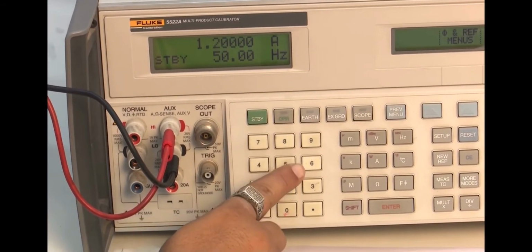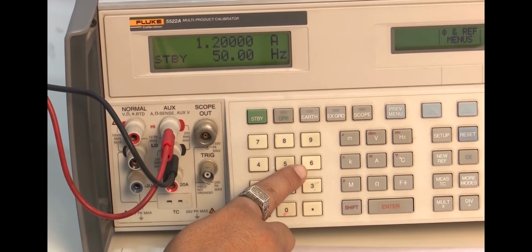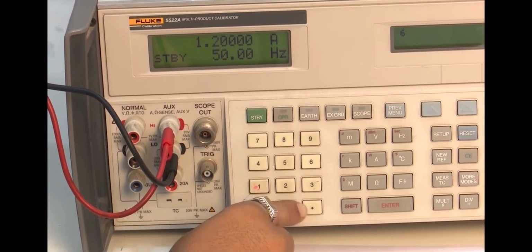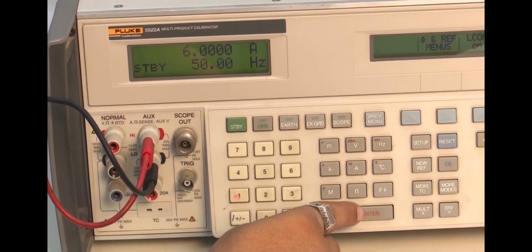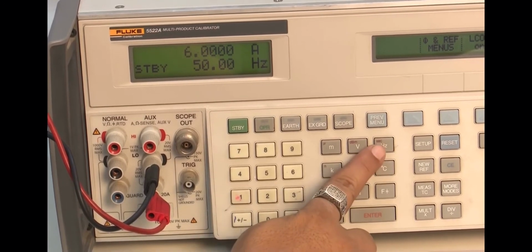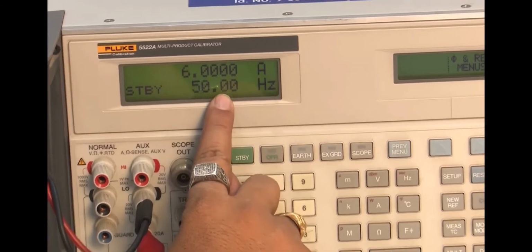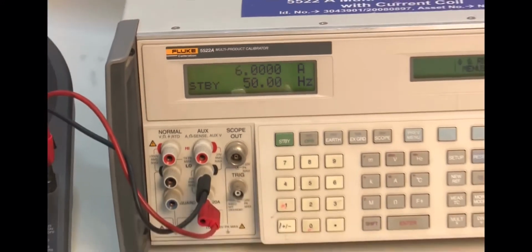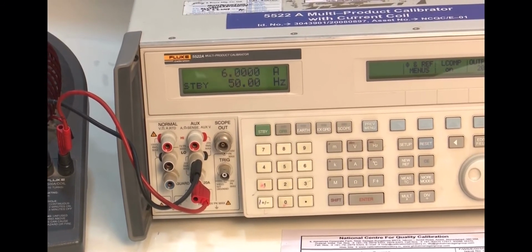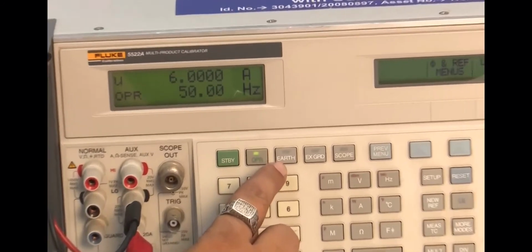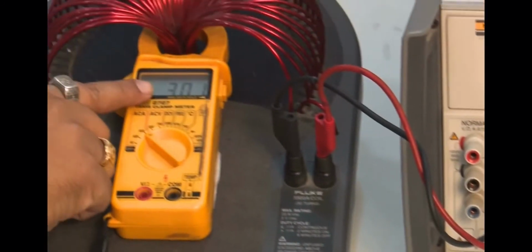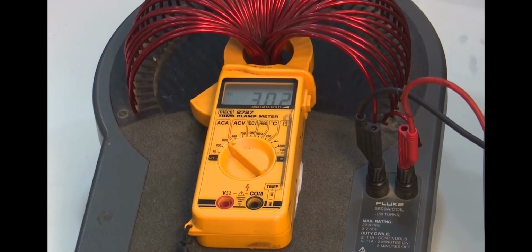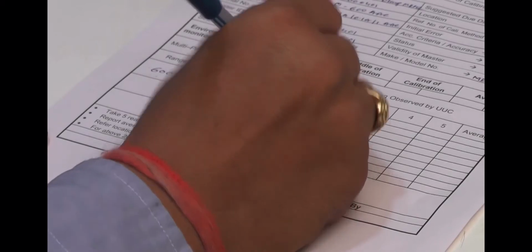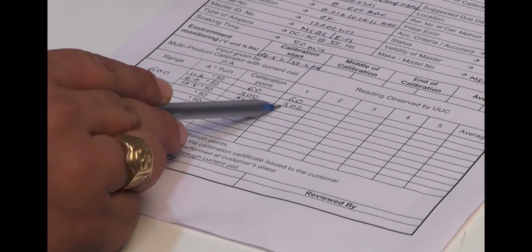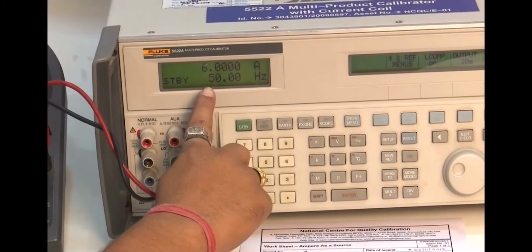Now I will proceed for second calibration point, that is 300 ampere. For this I am pressing 6 and then A, then enter and then pressing 5 and 0, then HZ, then enter. It means we have selected calibration point as 300 ampere at 50 Hz. Now I am pressing operate button to activate clamp meter and it is displaying 302 ampere. Again this reading is noted in the worksheet. This is called second calibration point. Then I am pressing standby button to stop output of multi-product calibrator.